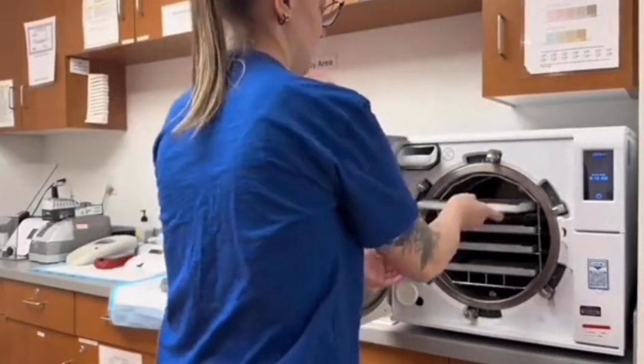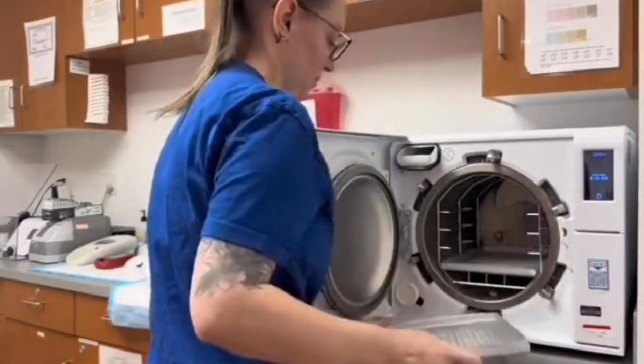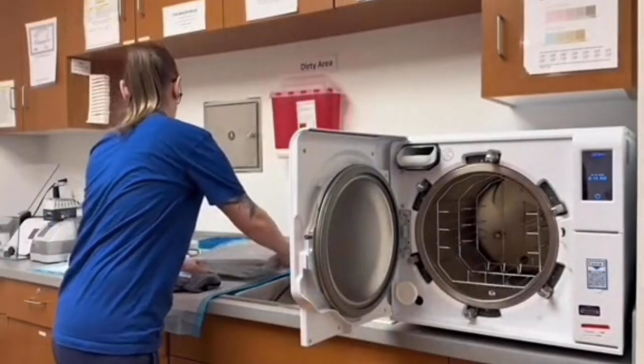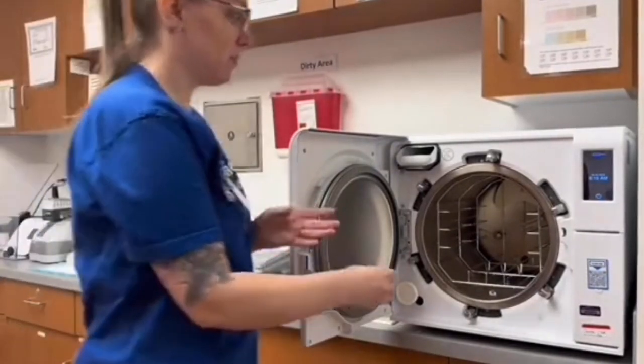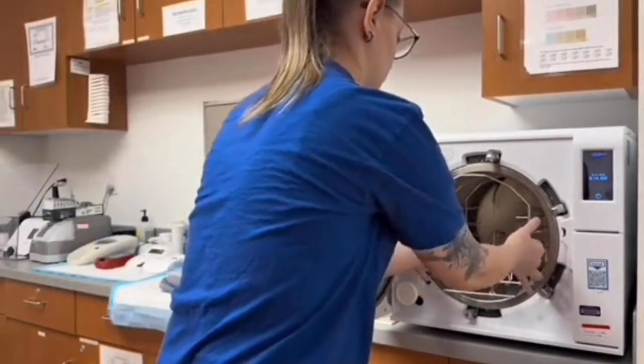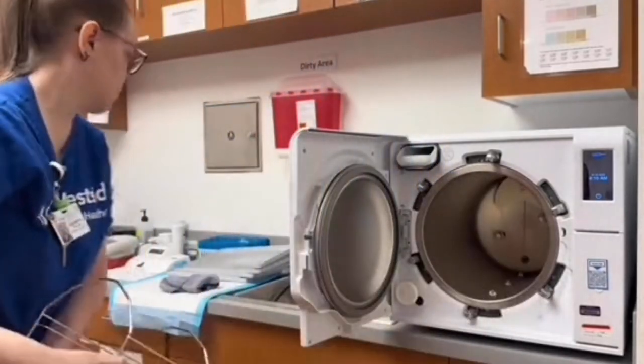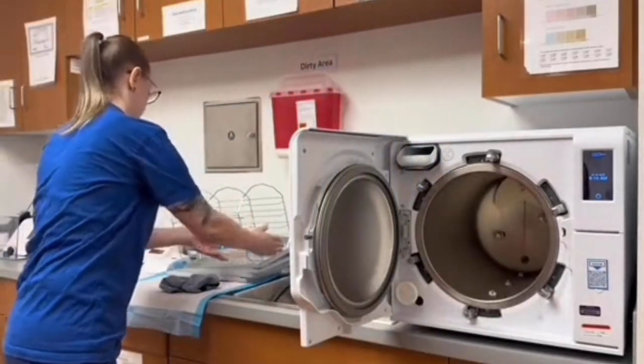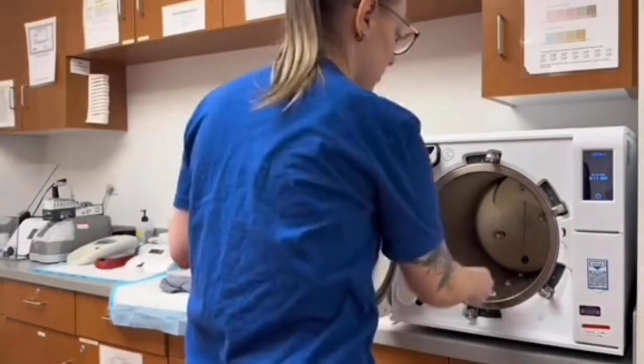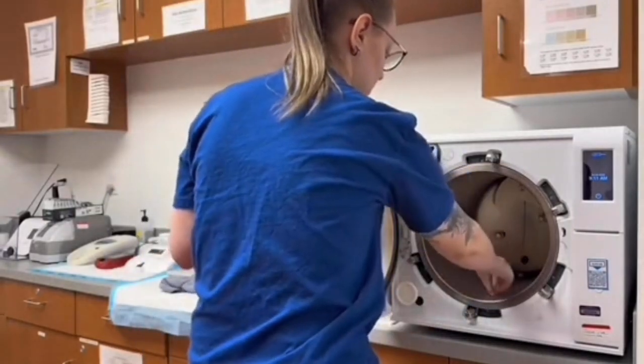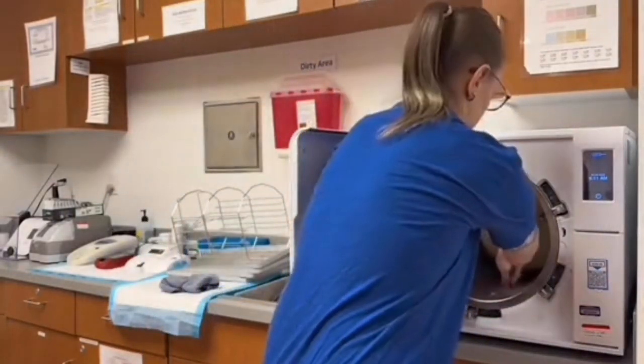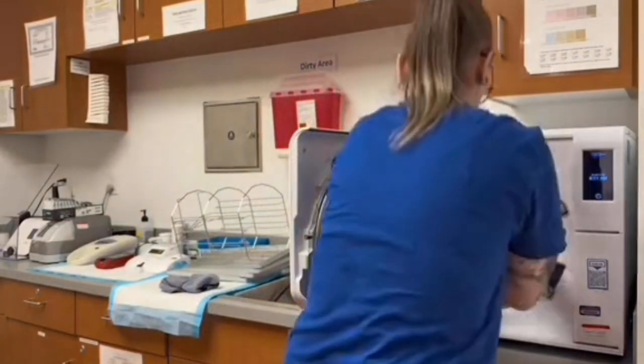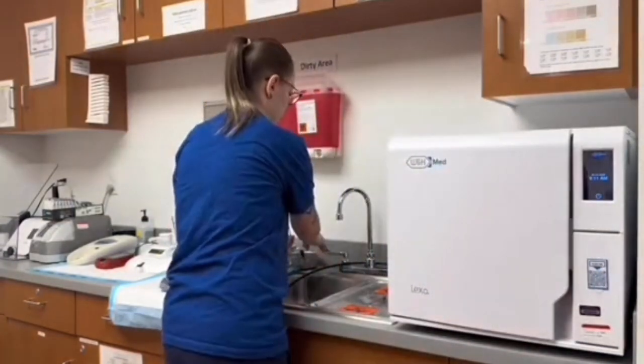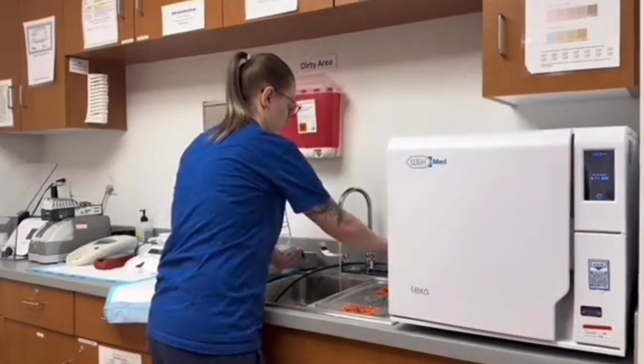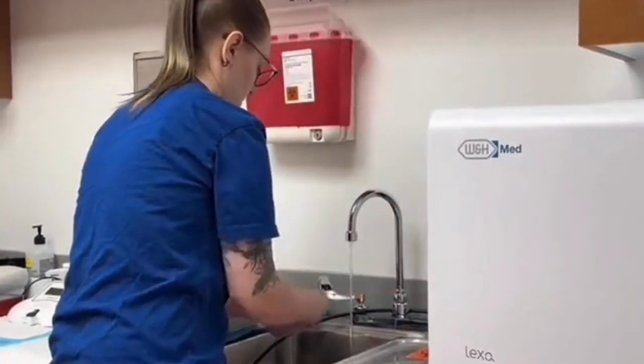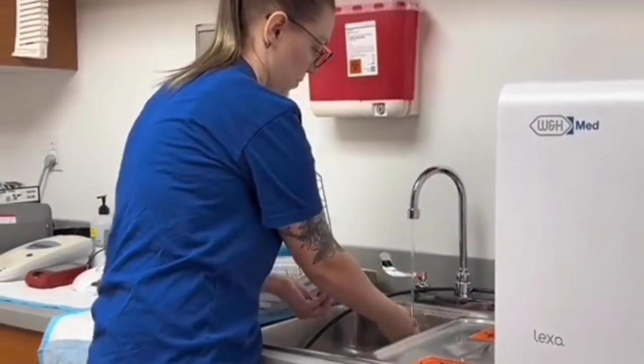Clean the machine once a month or after 50 uses, whichever happens first. Start by taking out the trays and the chamber rack, and then the filters at the bottom by turning them to the left. Rinse the filters with tap water to remove any debris and place them on a blue pad.